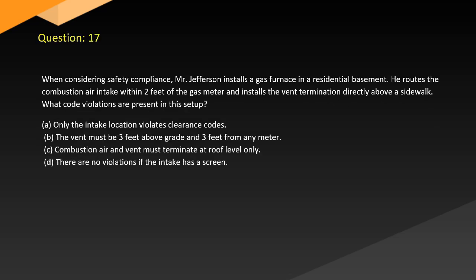Question 17. When considering safety compliance, Mr. Jefferson installs a gas furnace in a residential basement. He routes the combustion air intake within 2 feet of the gas meter and installs the vent termination directly above a sidewalk. What code violations are present in this setup?